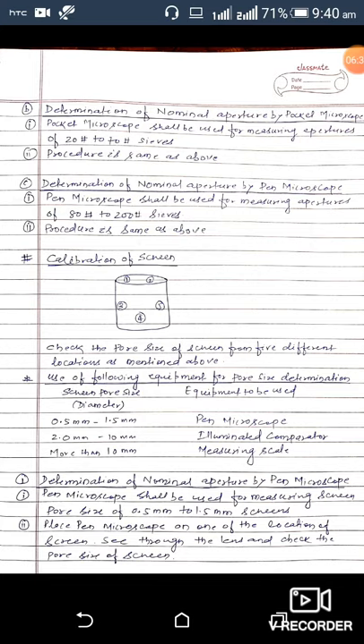The second point is determination of nominal aperture by pocket microscope. The pocket microscope shall be used for measuring aperture of 20 mesh to 70 mesh sieves, and the procedure is the same as discussed above. Third is determination of nominal aperture by pen microscope. The pen microscope shall be used for measuring aperture of 80 mesh to 200 mesh sieves, and the procedure is the same as above.